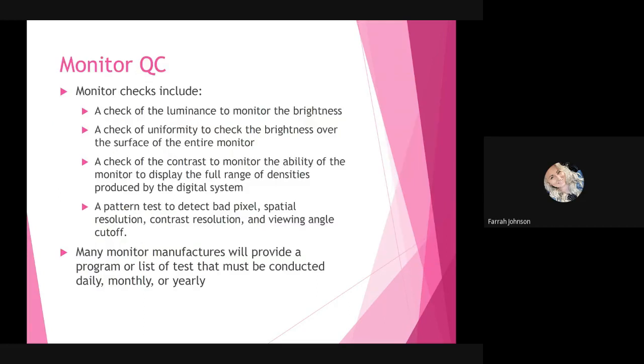So monitor QC, those checks are going to include a check of the luminance to monitor the brightness of the monitor. You also do a check of uniformity to check that the brightness over the surface of the entire monitor is the same. You do a check of the contrast to monitor the ability of the monitor to display the full range of densities produced by the digital system. So can you see all shades of gray that you would anticipate? And then also a pattern test to detect bad pixels, spatial resolution, contrast resolution, and viewing angle cutoff. Many monitor manufacturers will provide a program or list of tests that must be conducted daily, monthly, or yearly.